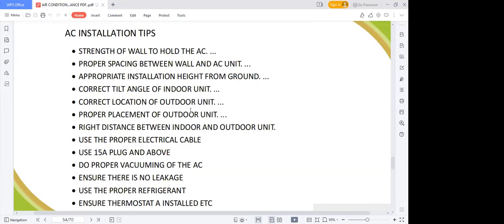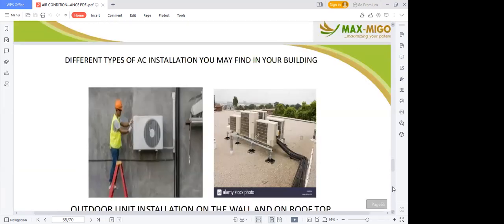Then an installation tip. Before you put anything on the wall, you must check the strength, proper spacing between the wall and the AC, appropriate installation height from the ground, correct tilt angle for the indoor unit, and correct location for the outdoor unit. All this, I believe you can read on your own. Then you see some professional installation being done. You see everything is perfectly straight. You see what this man is doing, perfectly done, using his PPE while maintaining. So you need to buy PPE for your guys. The PPE you might need includes your helmet, reflective jacket, safety shoes, hand gloves, ear muffs, or eye goggles, so that nothing will flash into their eyes and noise will not affect them.